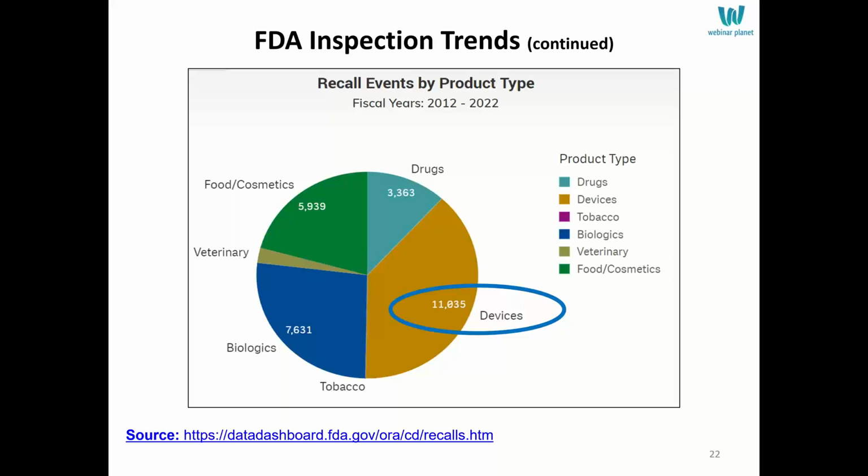As a result, they're following a quick process of, for example, incrementing, I should say, improving the system, giving new functionality incrementally, in small increments. They're changing things. But what happens is they're adding a function and at the same time they're not testing fully through regression testing that the rest of the software wasn't harmed. So they put in one feature and the next thing you know, the system breaks. Because of that, a lot of device failures happened.